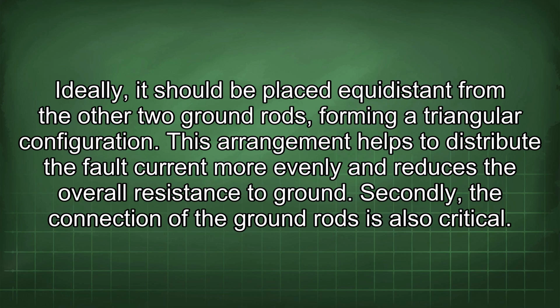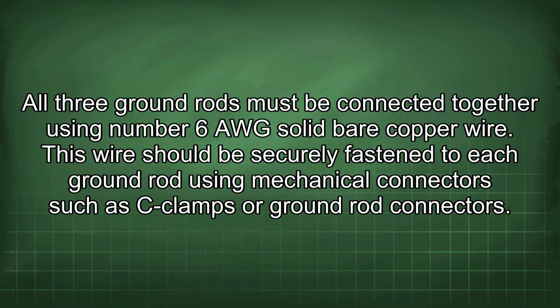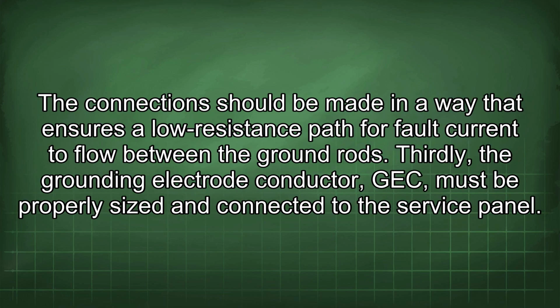Secondly, the connection of the ground rods is also critical. All 3 ground rods must be connected together using number 6 AWG solid bare copper wire. This wire should be securely fastened to each ground rod using mechanical connectors such as C-clamps or ground rod connectors. The connection should be made in a way that ensures a low resistance path for fault current to flow between the ground rods.